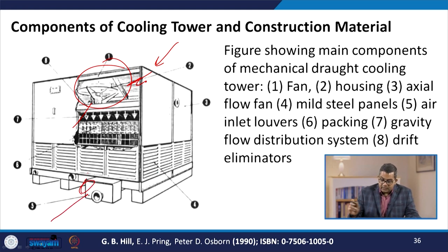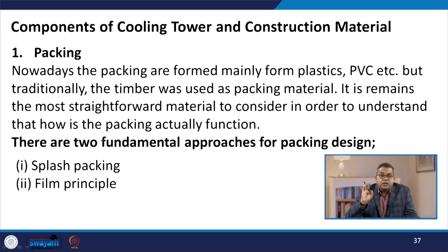Here you see the air inlet louvers, packing, and the gravity flow distribution system or drift eliminators. Now, when we talk about the packing, nowadays the packing is formed mainly from various polymers, polyvinyl chloride, etc. But traditionally, timber was used as a packing material in the previous era. It remains the most straightforward material to consider in order to understand how the packing actually functions.